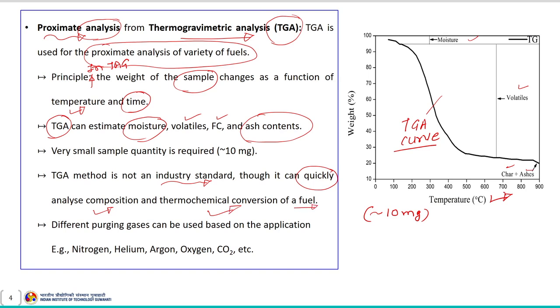Another advantage of this technique is that it can analyze different samples under different purging gases, and can be used based on the application. The purging gases that can be used include nitrogen, helium, argon, oxygen, and CO2. One of the most convenient advantages of this technique is that it can be carried out in a short span of time.